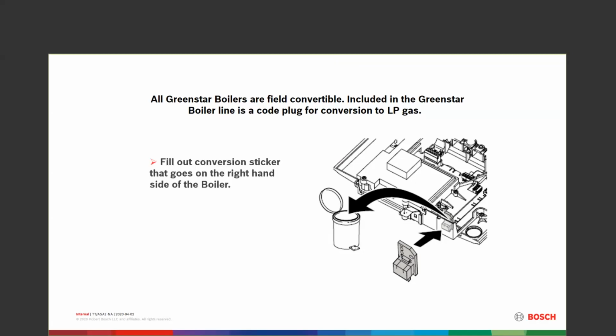You're going to pull that code plug out, the natural gas code plug, and put in the LP gas code plug. You're going to fill out the conversion sticker. Actually, I don't believe there's any filling out anymore. It's all filled out for you. You simply put it on the side of the boiler that it's been converted. And you must use an analyzer to do your gas adjustments, CO and CO2 have to be done.